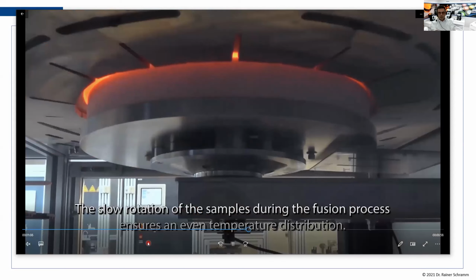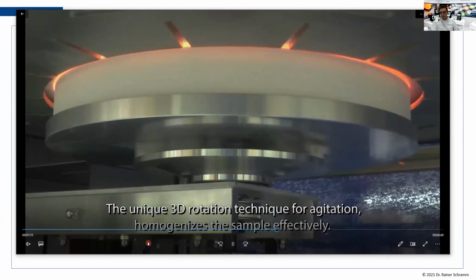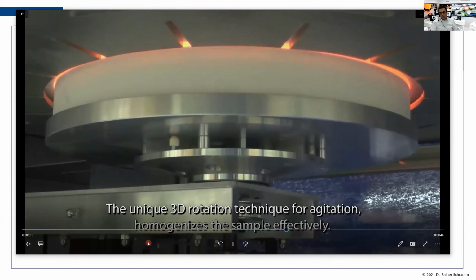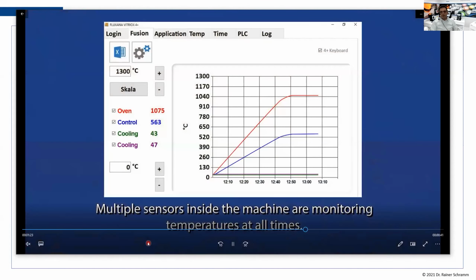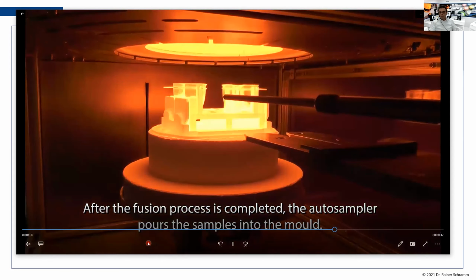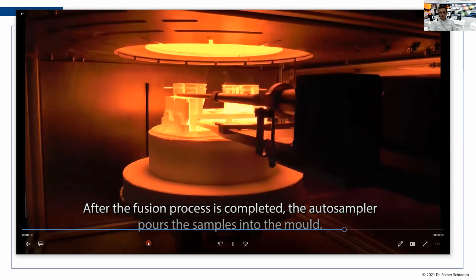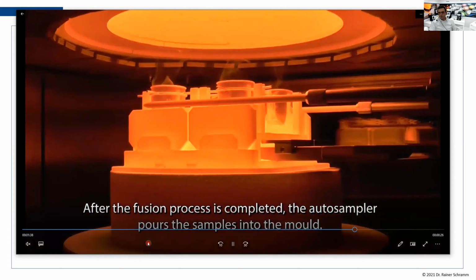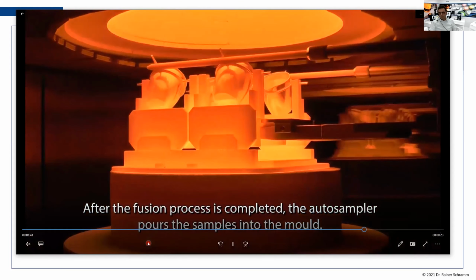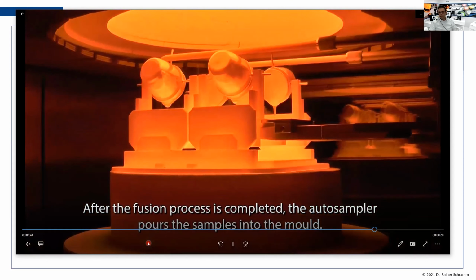This is the homogenization of the temperature. Like I said, it's turning all the time until it's liquid. And this is the high-speed agitation in both directions, so that you really mix it inside. Because all of our crucibles sit on a circle, it's exactly the same stirring for every crucible. Once it's finished, the autosampler comes back, takes the rack, and pours all 4 samples at once into their molds. In this way, we guarantee that every melt sees the same time and same temperature.